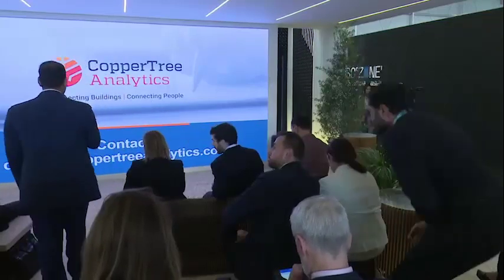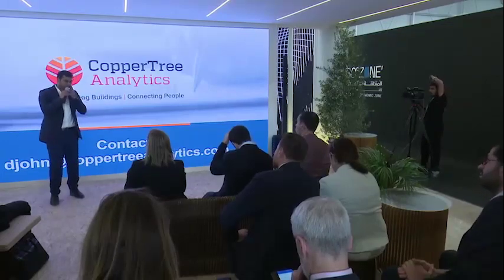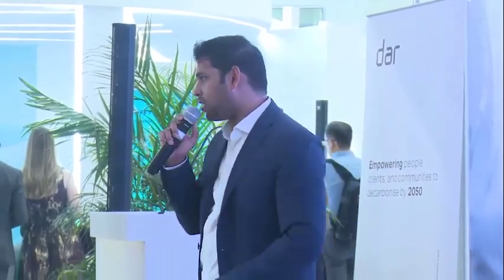Thanks for the question. It's an important one. Absolutely. Benchmarking is key because you can have, let's pick on a university campus as an example, buildings with a lot of lab spaces. They may be 200,000 square feet in terms of size, but the actual consumption within the building will be way higher than a 400,000 or 500,000 square feet building, which is an admin building. And so it's really important to make sure that when you're comparing buildings, weather normalization and all of the other normalization elements that we talked about still apply, but you've got to group the correct buildings together. Otherwise, you're not comparing apples to apples.